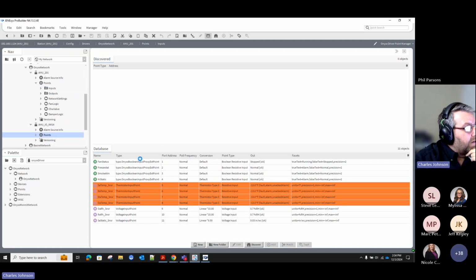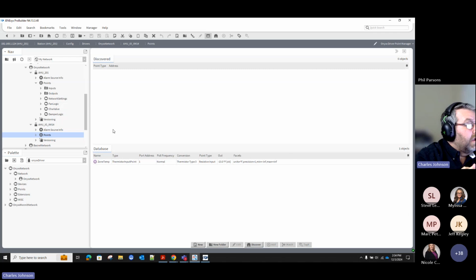But since I've configured an input here in my XM IO, let's go ahead and configure an output. We have two types of outputs: digital outputs, which are actually relay outputs, not triacs, and a voltage output, which is 0 to 10 — it cannot do 4 to 20.